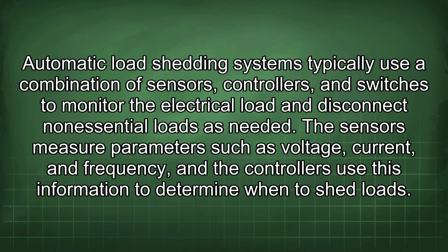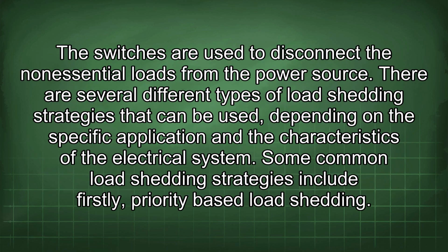Automatic load shedding systems typically use a combination of sensors, controllers, and switches to monitor the electrical load and disconnect non-essential loads as needed. The sensors measure parameters such as voltage, current, and frequency, and the controllers use this information to determine when to shed loads. The switches are used to disconnect the non-essential loads from the power source. There are several different types of load shedding strategies that can be used depending on the specific application and the characteristics of the electrical system.